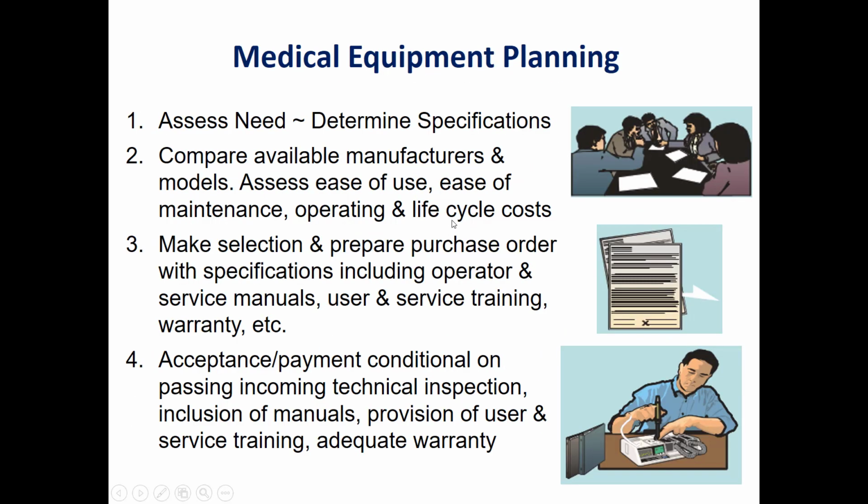So now I will start with the first policy and procedure, which will be in the planning part. In this policy, if we need to buy a new medical device, what are the steps of the policy related to procurement or purchasing a new medical device? First of all, we should assess the needs, make a needs assessment.